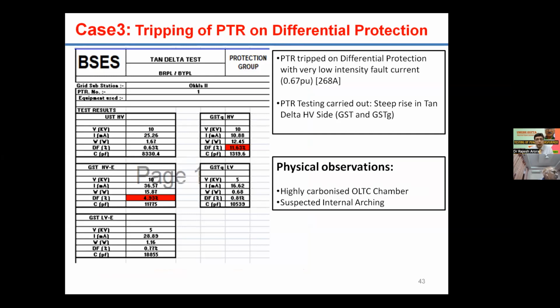Now come to the next case where a power transformer tripped on differential protection with a very low intensity fault current. This was a 20 MVA transformer and its full load current is 350 amperes, and we observed that it tripped on differential for a mere current of 270 amperes. Thereafter, we conducted all the electrical tests on this transformer: magnetic balance, winding resistance, short circuit, TTR. All the results were found satisfactory.